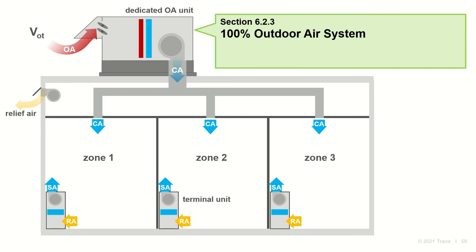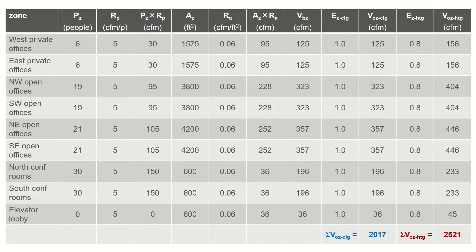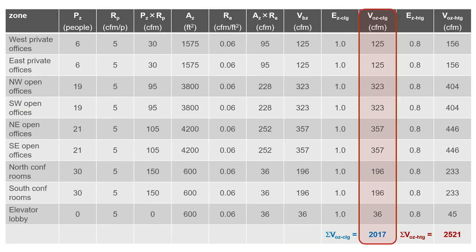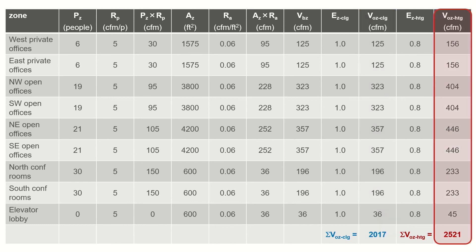Moving on to the 100% outdoor air system: a dedicated outdoor air unit delivers conditioned outdoor air directly to all zones on the floor plate, with a local terminal unit in each zone for cooling or heating. Since the ventilation system delivers only outdoor air and no recirculated air, the required system intake flow V-sub-OT equals the sum of the zone outdoor air flows — 2,017 CFM if E-sub-Z is 1, or 2,521 CFM if E-sub-Z is 0.8.